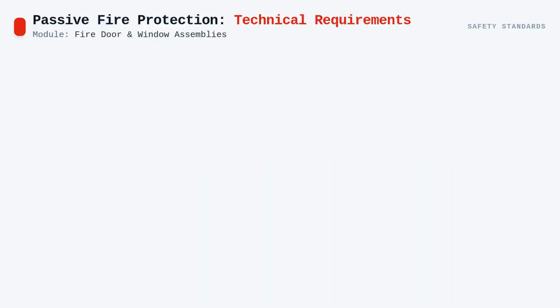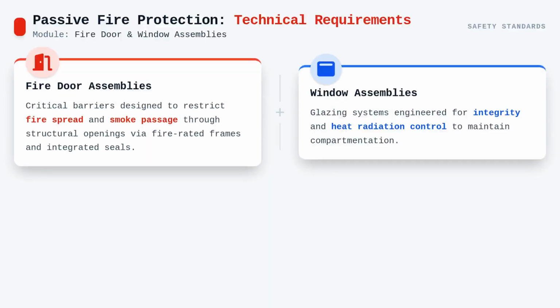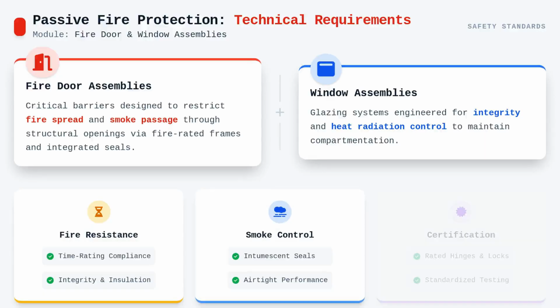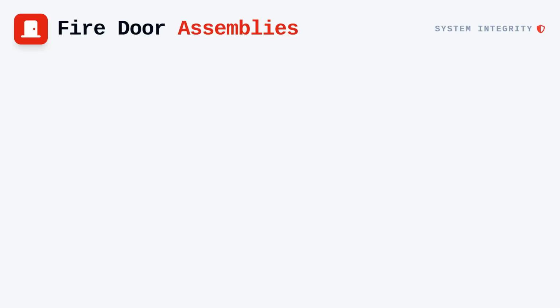Welcome back. Today we examine the technical requirements for fire door and window assemblies within the scope of passive fire protection. Fire door assemblies represent a dynamic component of fire-rated construction that must maintain barrier integrity under extreme conditions. Unlike fixed walls, these assemblies must balance egress functionality with the requirement to resist fire, smoke, and heat transfer. When a building is subjected to a fire event, the door assembly acts as a critical seal, preventing the migration of toxic gases and thermal energy between compartments.